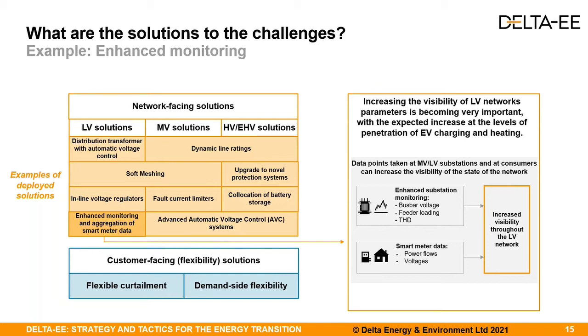And what we have seen happening more and more is that this visibility is now being increased. This is done, for example, by replacing the traditional maximum demand indicators at a medium voltage to low voltage substation with more sophisticated monitoring that looks at busbar voltage, feeder loading in detail, and harmonic distortion at this level.